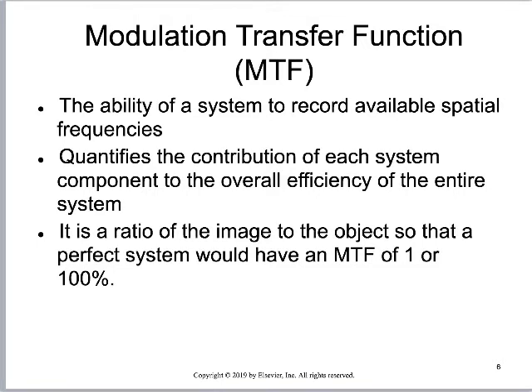If the system can see smaller and smaller lines, it has a better and better modulation transfer function. MTF is expressed as a percentage value. The flat panel detector system, particularly the direct radiography system, is going to consistently have the best MTF — we want a number close to 1, where 0 to 1 represents 0% to 100% representation. The closer to 1, the better the system can represent that tiny object.